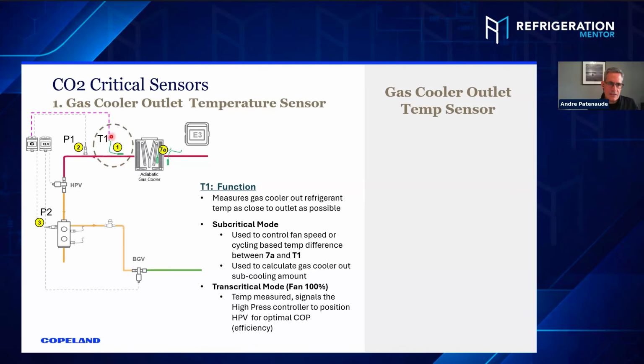So it sends a signal to the high pressure control, right? And that's one thing. And it's also calculating the TD between my pre-cool sensor 7A and my T1 sensor for fan speed. So that's number one. But when it's in subcritical mode, it's also sending a signal to the controller to say, hey, high pressure valve, you need to maintain X pressure to maintain a subcooling.